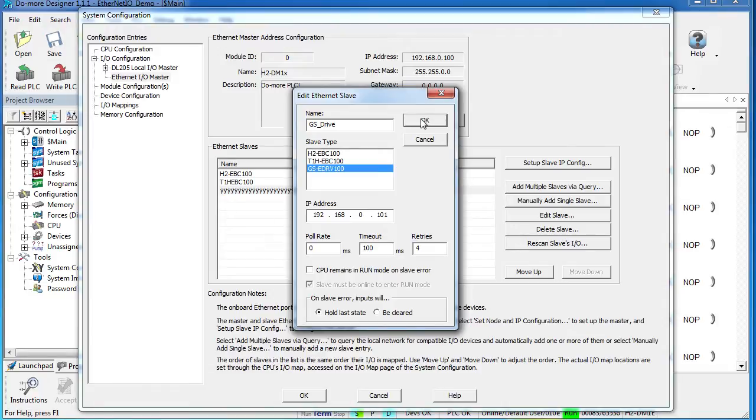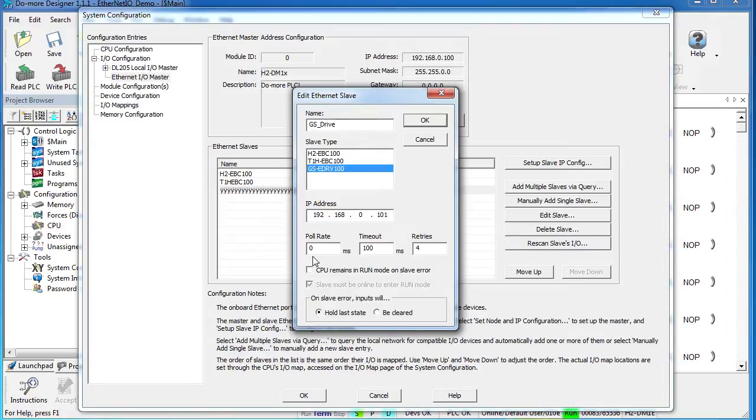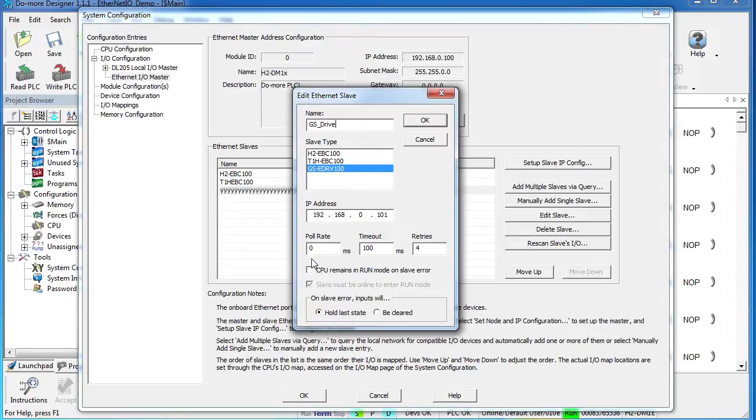Either way you access this dialog, one thing you definitely want to keep an eye on is this poll rate. A zero says poll as fast as you can. So if all devices are polling as fast as possible, this Ethernet I.O. feature has the potential to consume every bit of bandwidth available, which may be okay for your setup. But for me, I like to limit these to something reasonable so I have bandwidth available for other things I might want to use the Ethernet port for, like C-more Micro HMIs.